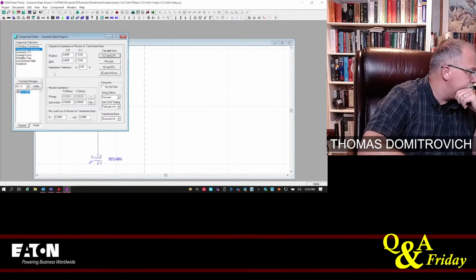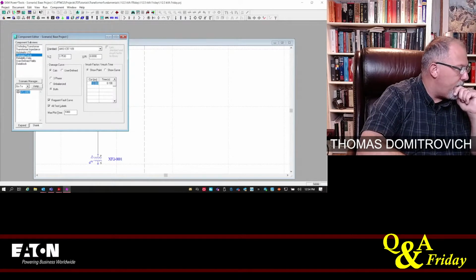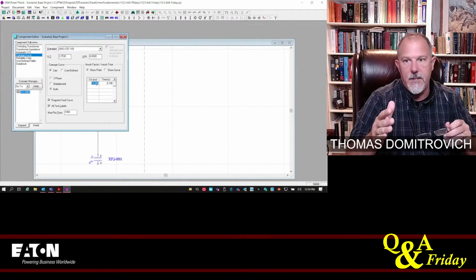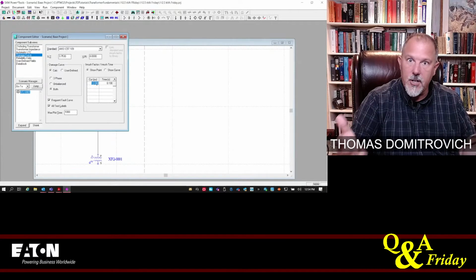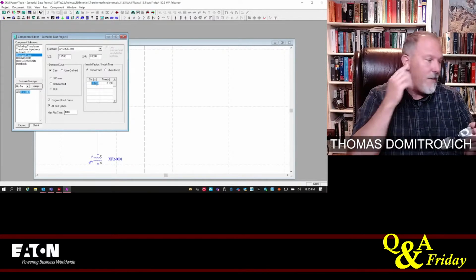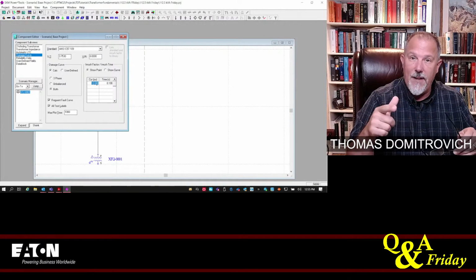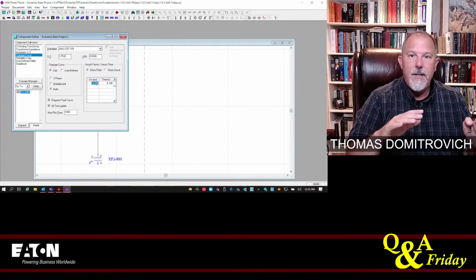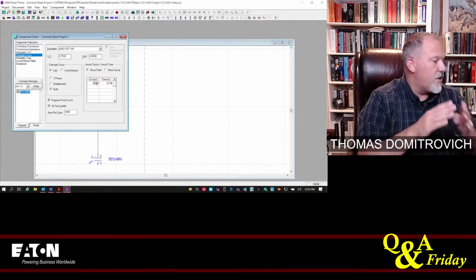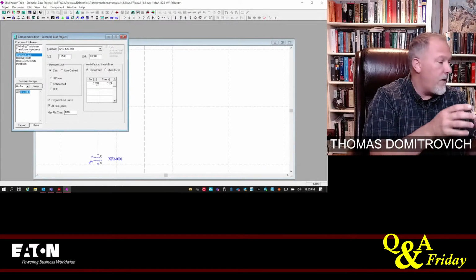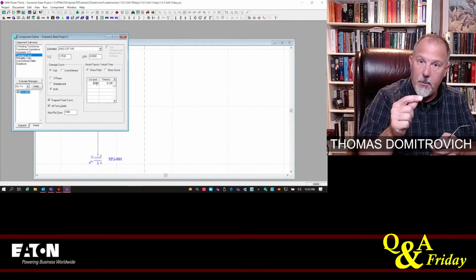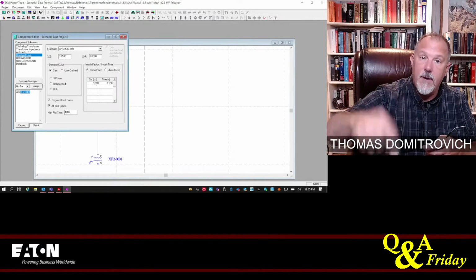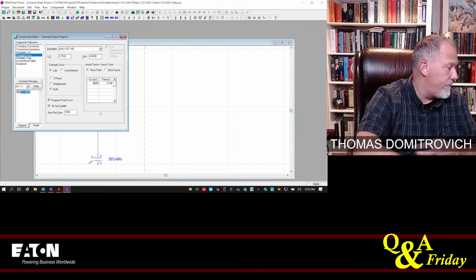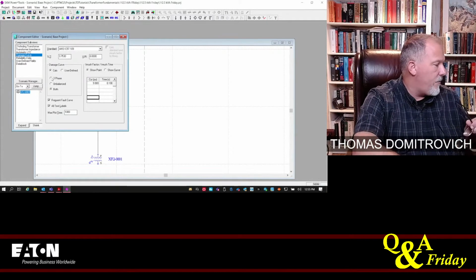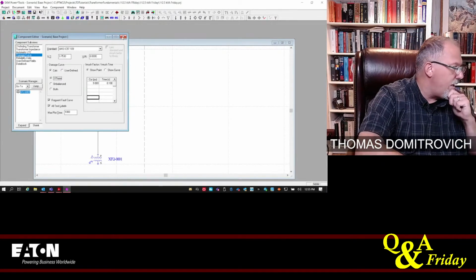All right, so damage curve. So when I look at the locked rotor inrush, the locked rotor amps. It's a transformer. The inrush current. When I look at my inrush current, we looked at some tables and did some homework with regard to a couple manufacturers, and we saw none of them got up to 12. They got around 8 to 9. So I'm going to make this a 9. So it's 9 times the primary full load amps for 0.1 second duration. It'll be a data point, and I have to make sure that my instantaneous of the primary overcurrent device is greater than that number. All right. I will just do my 3-phase fault, and that'll be that. So there's my transformer.